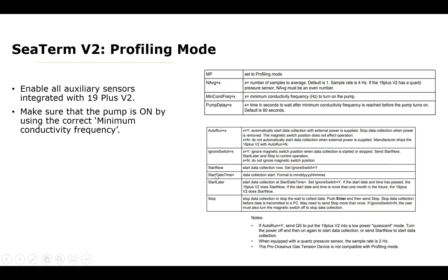And furthermore, you will perform these particular setups, such as the pump delay, or when you want the instrument to start sampling, when to stop. An important note I will make is very specific to the magnetic switch that we just covered in the physical overview. Switching that on and off basically means you collect data, which is on, and off means you do not collect data. This table gives a really good depiction of how to use those particular commands with the magnetic switch on and off.